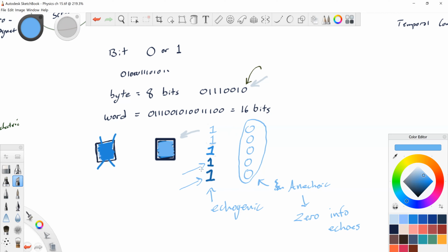And that information was turned into a voltage, and that voltage went up into the machine, and the machine said, I'm reading this now as a 00011. Well, probably still hypoechoic, but getting a little brighter, definitely there on our screen. And then the echo became stronger, creates a stronger voltage. That voltage is read as more ones, and eventually we get to the point where we cannot have any more ones. In other words, you cannot get any brighter on the screen. Echogenic.